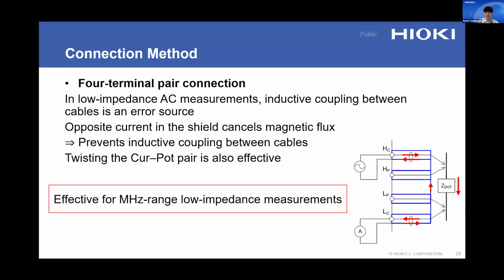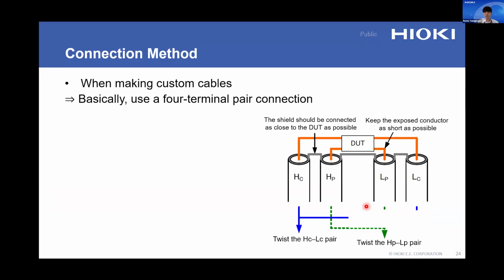This method is called the four-terminal pair connection. It is particularly effective for low impedance measurement in the megahertz frequency range, where inductive coupling becomes significant. In addition, twisting the high-low pair for both current and voltage lines is also effective in reducing inductive coupling. Our optional measurement leads for LCR meters basically use this four-terminal pair connection. If you make your own cables, it is effective to design them so that they can operate in the same way. In this method, each shield conductor needs to be shorted in order to return the measurement current.